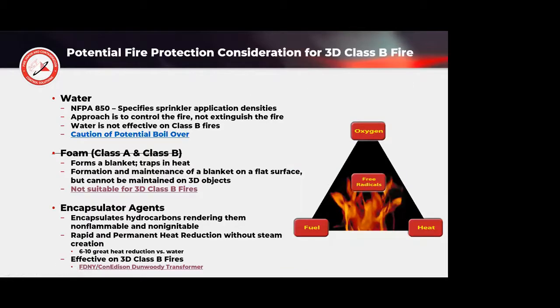So again, we look at, okay, we have options: water, foam, encapsulator agents. NFPA specifies sprinklers, but again, it's to control the fire, not extinguish the fire. Water's not effective, and too much water can cause a boil over. I don't think that hyperlink's going to work. Again, we've already talked about foam, not suitable for a three-dimensional fire.